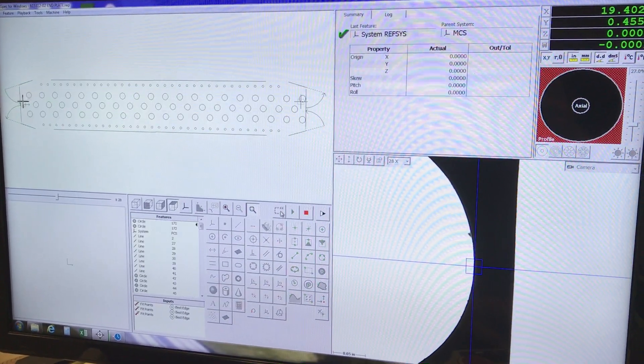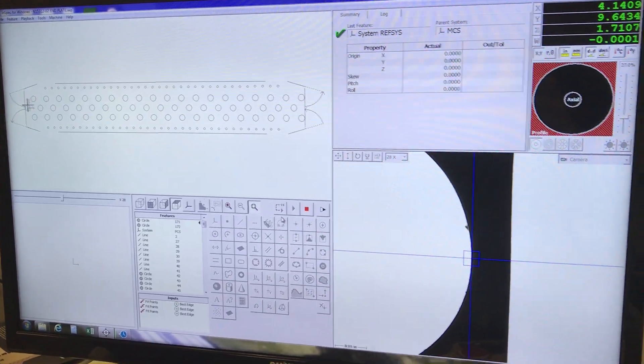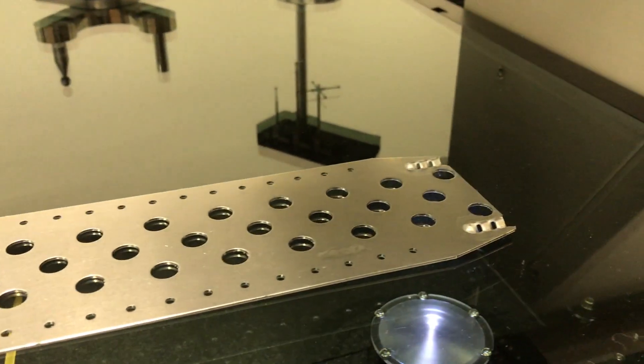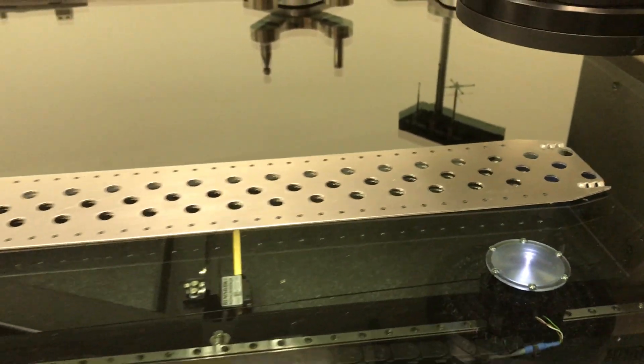I'm going to choose the Rerun button. The machine then drives over and starts aligning the part. It does this by measuring several of the key circles, setting up an alignment off two of the circles and an origin point.